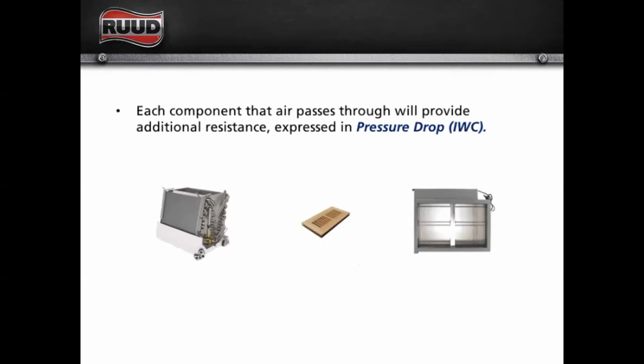Again, each component that air passes through is going to add resistance. That's going to give us a pressure drop, and all of those pressure drops throughout our whole duct system are going to add up, and they're going to affect the static pressure that we're operating against, and they're going to affect the amount of air that we can move through the duct system.